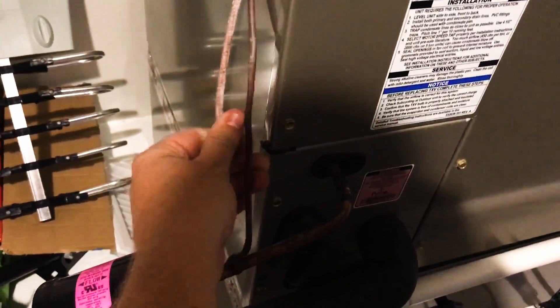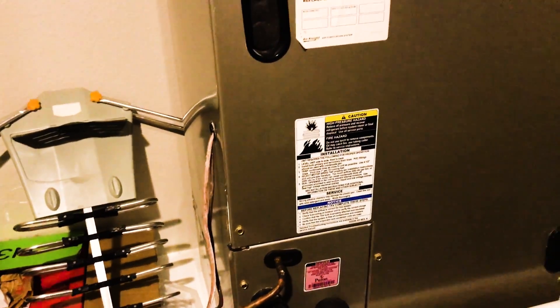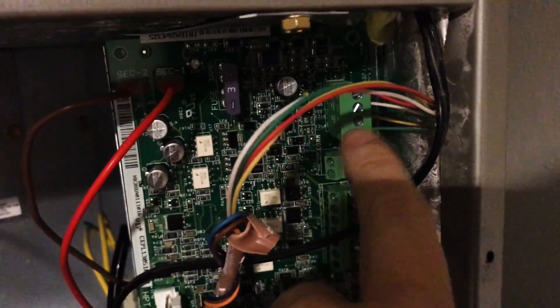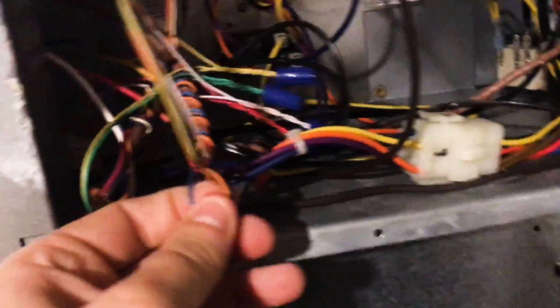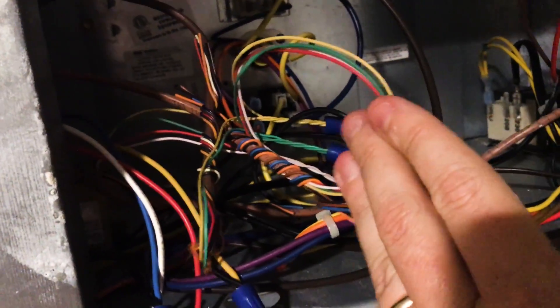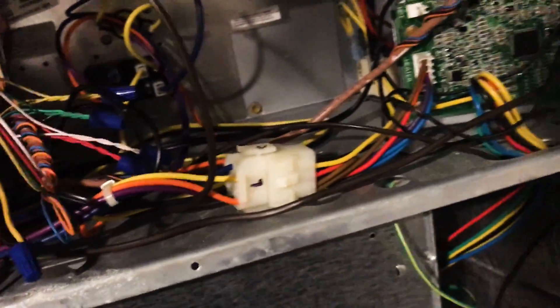I'm going to do a fix I've heard a couple of times that helps when you didn't run shielded cable with communicating systems. Right here you can see regular thermostat wire — we have four leftover conductors, which can serve as a sort of shield by grounding them on one end. Our ABCD connectors — green, yellow, white, red — are all we're using for 24 volts and communications. When using unused conductors as shielding, you only connect them on one end to avoid creating a ground loop.